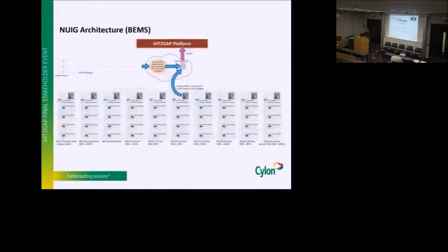So the challenge that we had on this site, as I mentioned, it was a Unitron site. So you can see these trunks here are all Unitron. They're all proprietary protocol, and that gives us a problem with actually getting the data where it was needed. As I mentioned, we did have Aspect, and that sits in these Aspect control engines. They were much better at pushing data because it's something that they did already. The challenge for us was to actually take the Unitron data, get in with Aspect so that we push that forward.